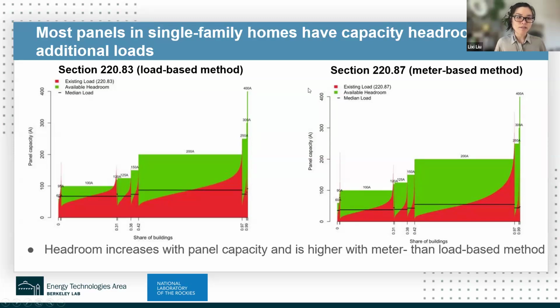Here we have the calculated panel capacity headroom. The good news is that most single-family homes already have room to add new loads without a panel upgrade today. These two charts show connected load in red and available headroom in green across homes grouped by panel size from 60 to 400 amps, sorted by available headroom.